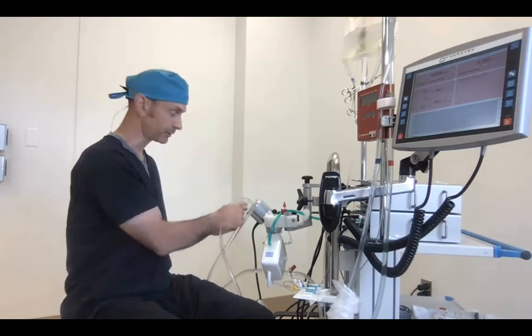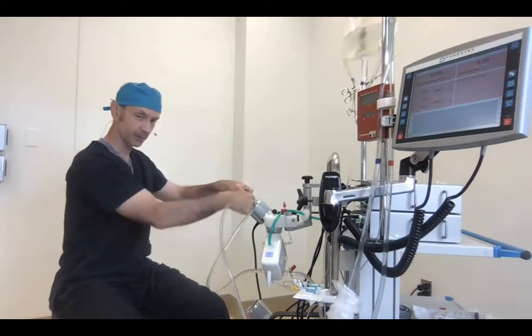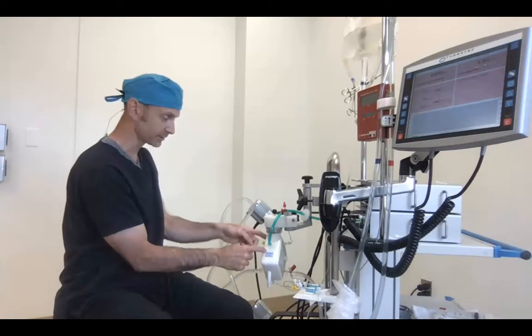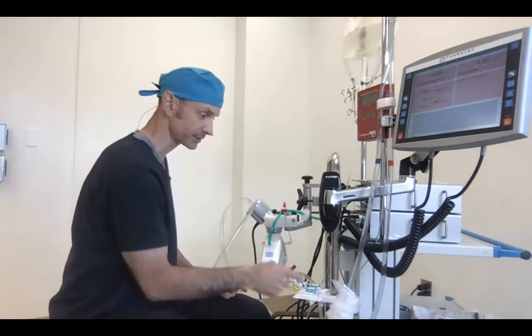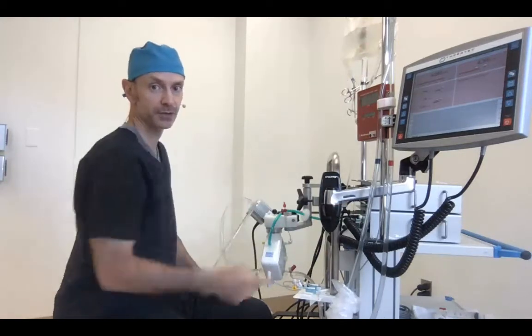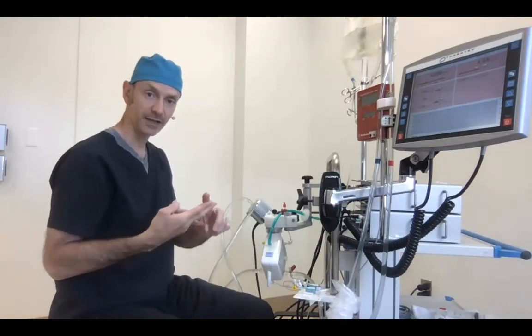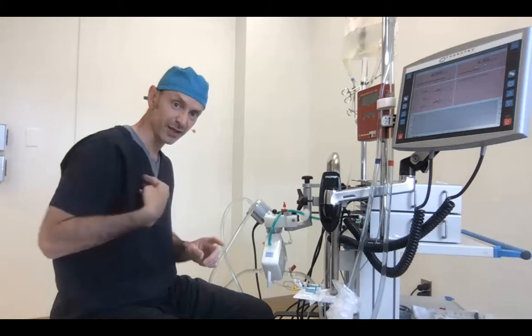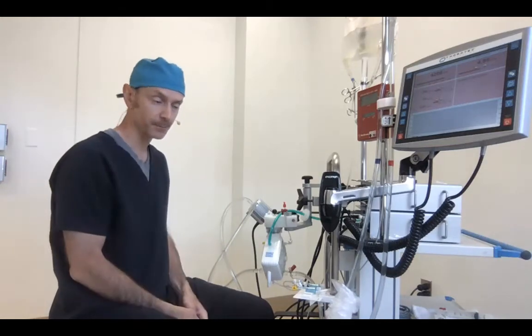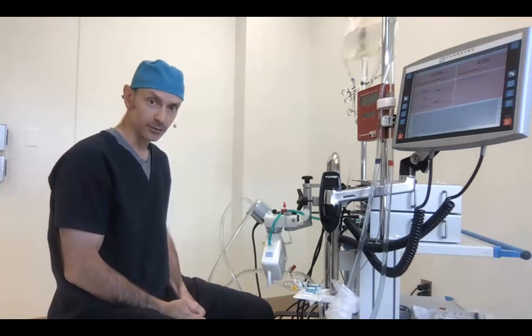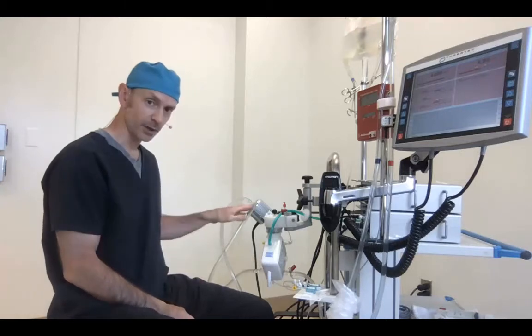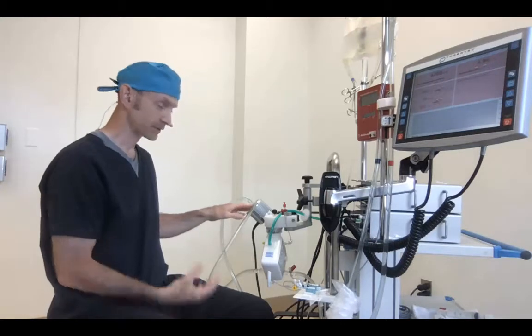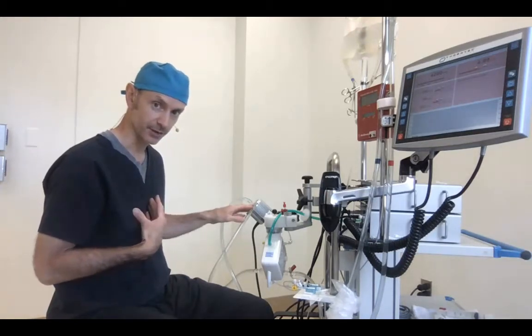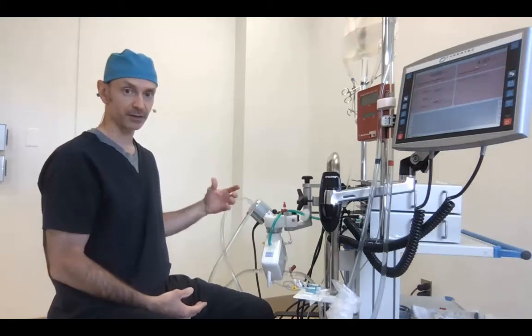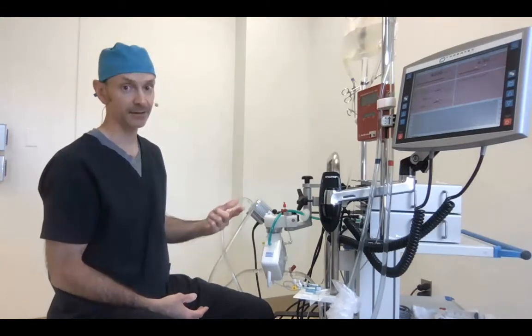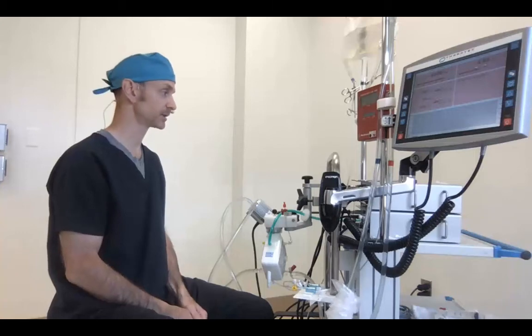And it's also afterload dependent. So what would be the afterload of this pump? That's everything after the pump. So it's this piece of tubing before it gets to the oxygenator. It's the oxygenator. It's the arterial line all the way up to the patient. It's the arterial cannula. It's the SVR of the patient. It's the position of that cannula inside the patient as well. All those things contribute to the afterload of this pump. And just as it is with your native ventricle, if the pump has difficulty emptying, if it has a high afterload, then it pumps less well.